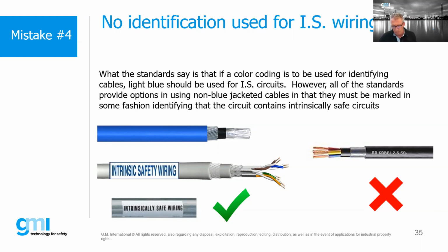Also, when it comes to inspections, a lot of things with intrinsic safety allow us to use non-certified products in areas that might be hazardous locations if we're using intrinsic safety. If I'm an inspector walking into a facility and I see non-certified glands or non-certified pieces of equipment in a hazardous area, that should immediately be a red flag.